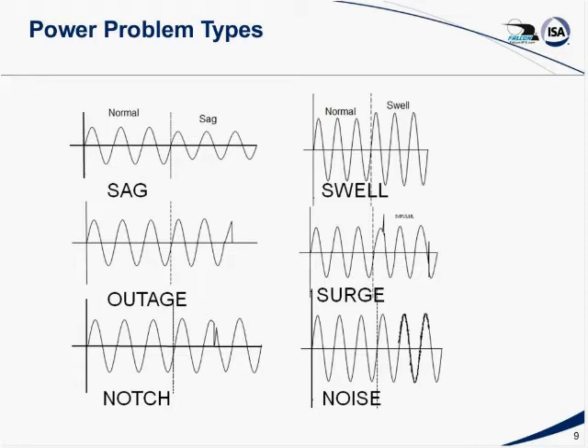We have harmonic distortions, not shown on this slide as such, but generally they will distort the wave shape, which causes heating in many of your inductors, and if it's of the triplen type, will cause heating in your neutral. Those are just a few of the power problem types that have to be addressed by a UPS.